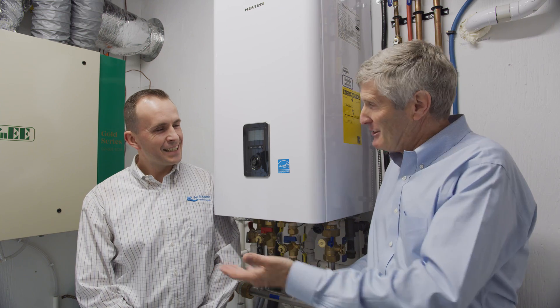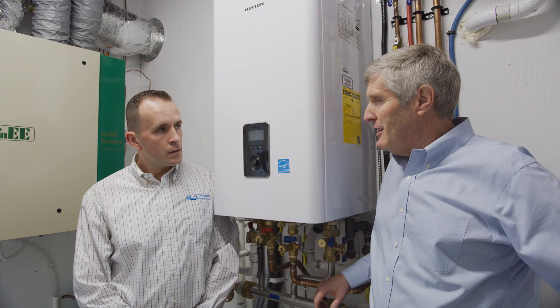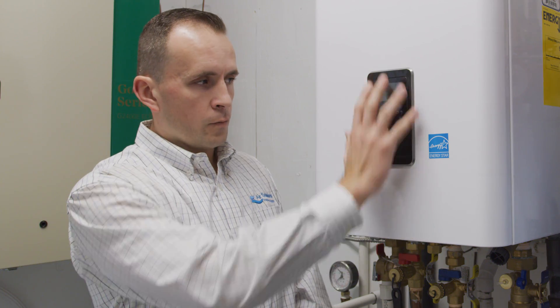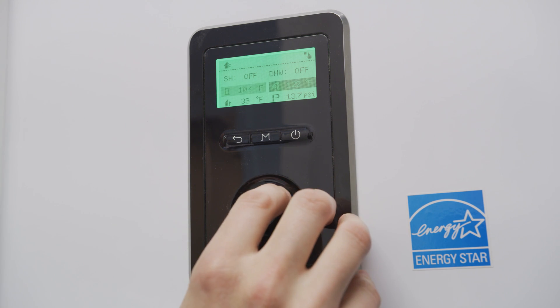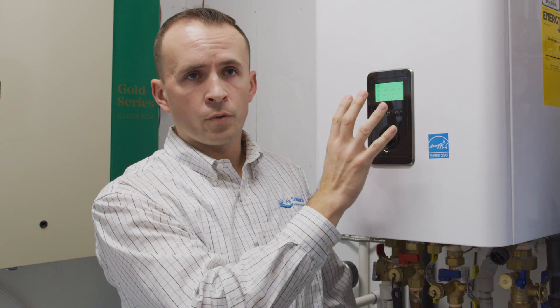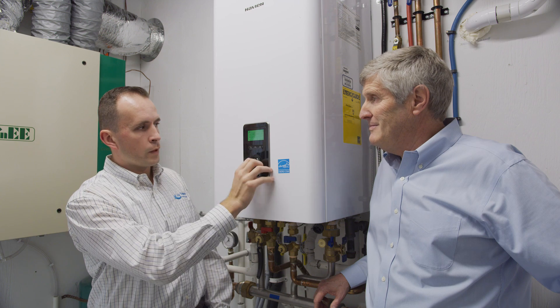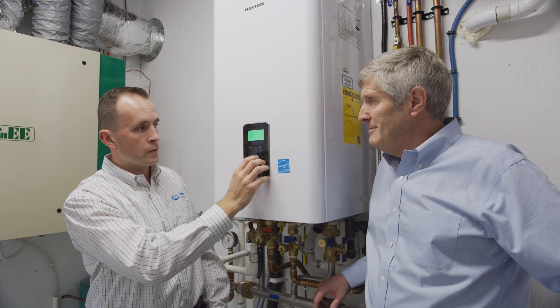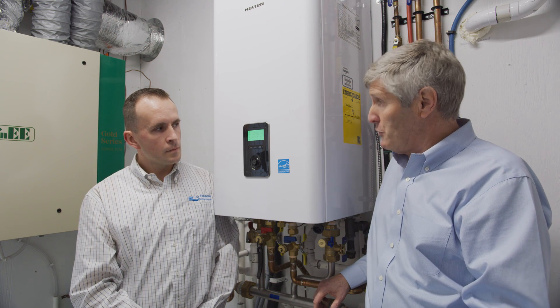People always ask when they come to these kinds of projects: I want to see the mechanical, it must be really complicated. And they look at this and it's actually pretty simple. Navien's newer rotary knob control — the screen lights up as soon as you start interacting with it, and on your standby screen you're going to have everything you really need to know about whether this product is operating as intended. You've got your domestic hot water set point, your space heating set point, and you can easily change them. The key here is I can set my hot water temperature at something nice and safe in that 120 degree Fahrenheit range, but the in-floor wants to run significantly cooler than that.